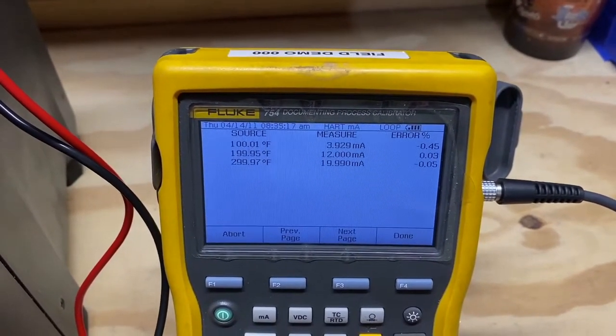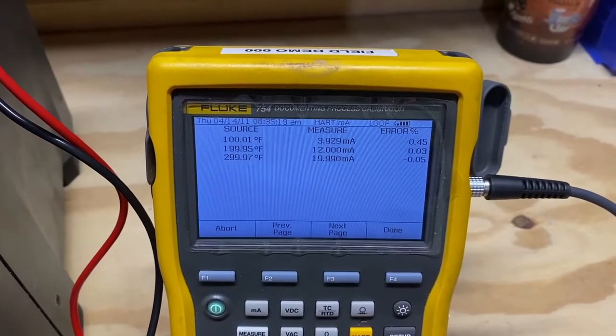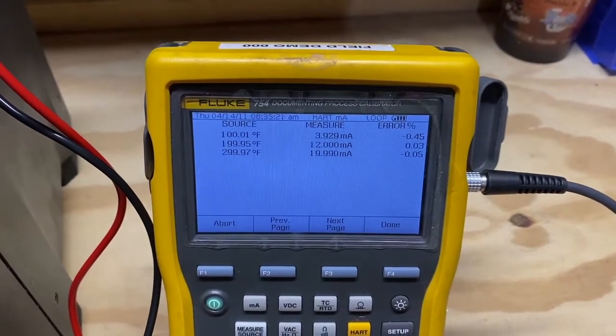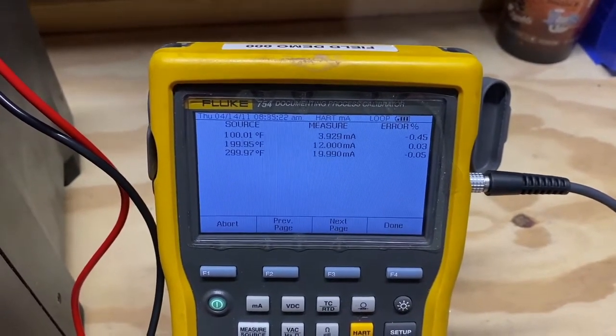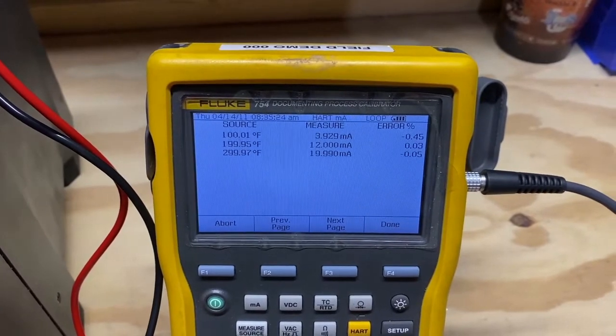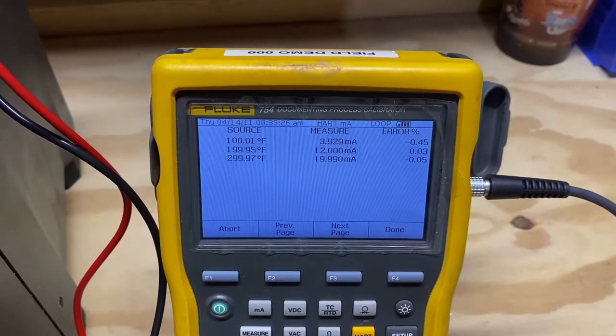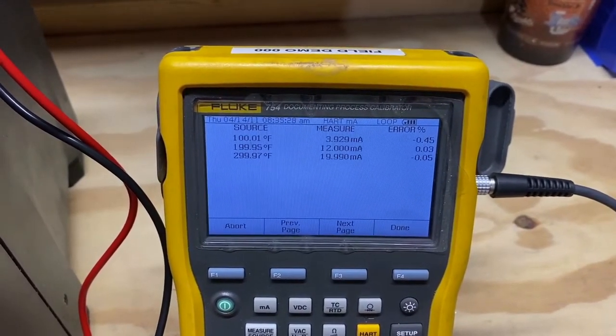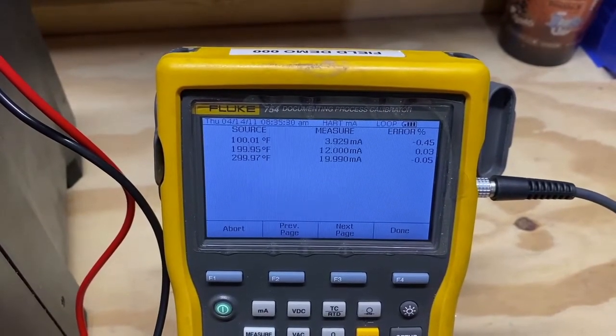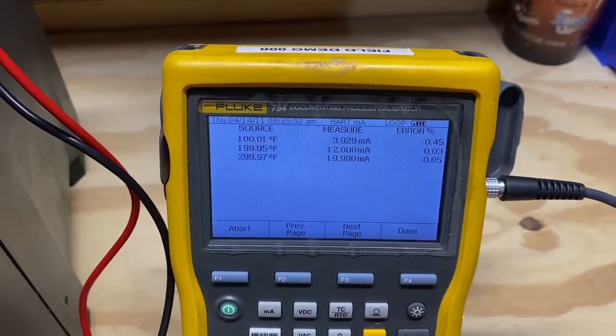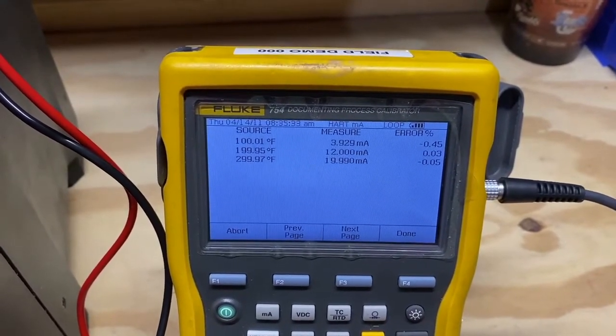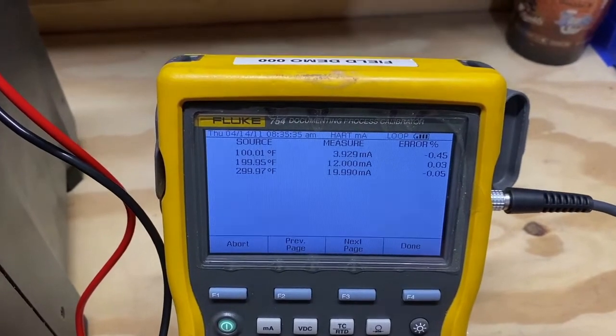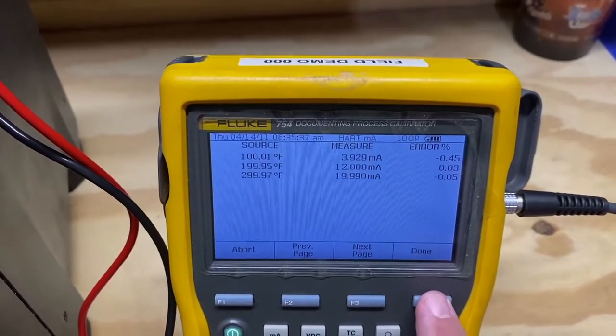Upon completing the calibration cycle, the 754 will list out the documented results of the source, the measurement, and the percent error capture. In this example, there was no error percentage outside of the 1% threshold we had set, so there is no reverse video overlapping the actual lines of error percentages. To complete the test, we will hit Done.